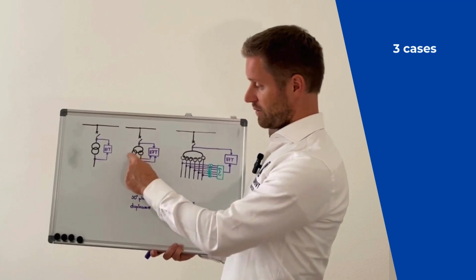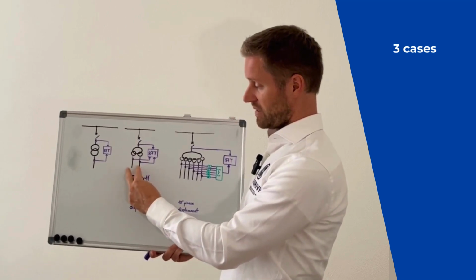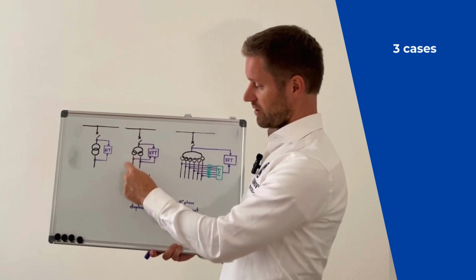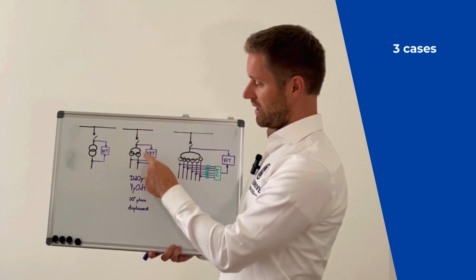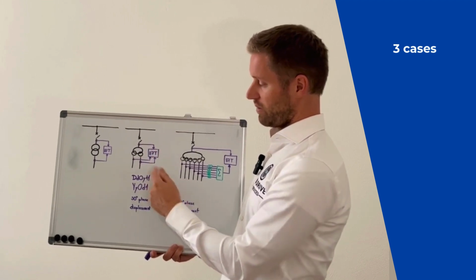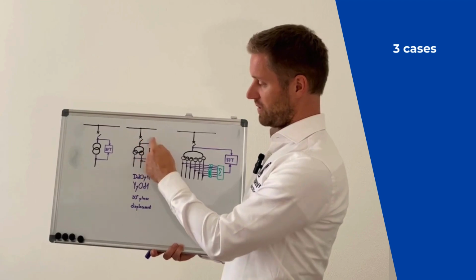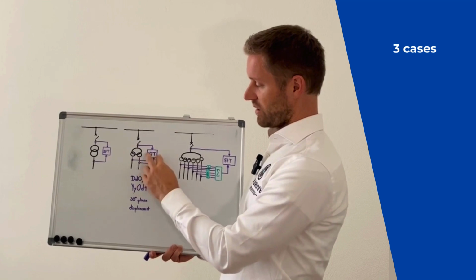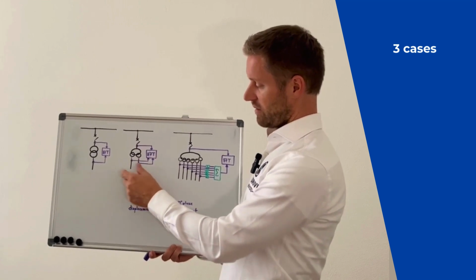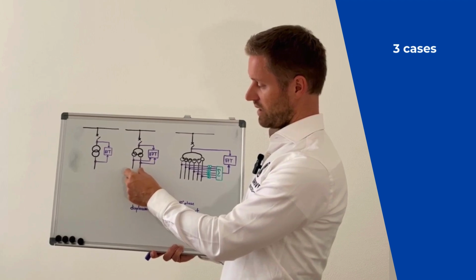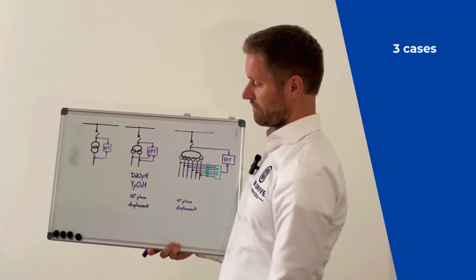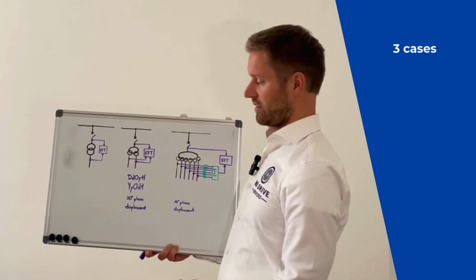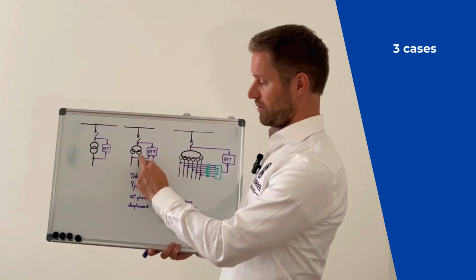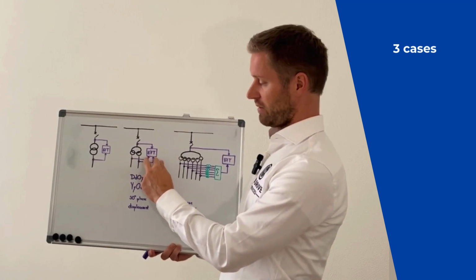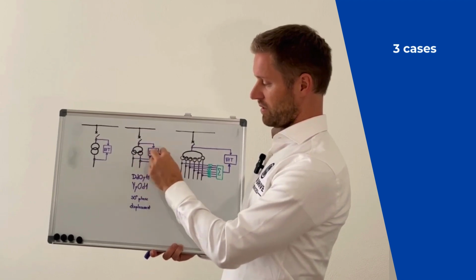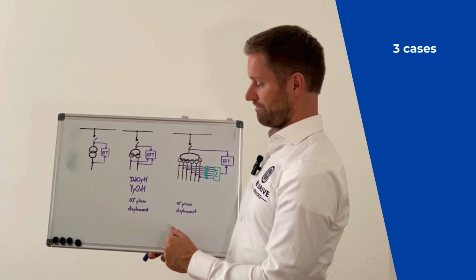But the point here is that we have two secondary windings with 30-degree phase displacement, but on such a still relatively simple configuration, the protection relay would support it. So we can just feed the primary measurement inside and the two secondary measurements. The currents are phase displaced, they are not in phase, but the relay would consider that internally in the calculation. So it would sum those two secondary currents in a correct way, geometrically. It would consider the phase shift.